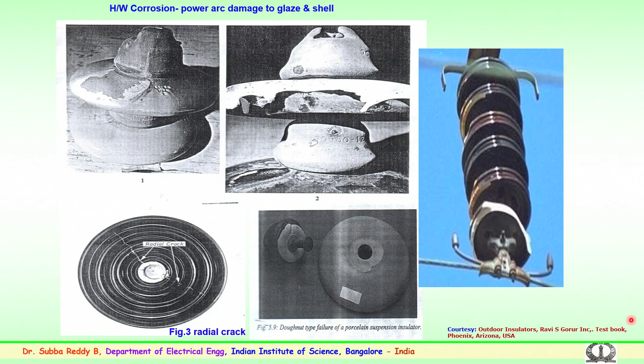This again is a typical example of the lightning phenomenon striking the insulator assembly, where due to the lightning the failure of the insulator assembly has happened. Several of these failure modes have happened due to hardware corrosion. The damage could happen at the pin junction where the Portland cement gives way, or the growth of cement could damage the insulator and help in the puncture of the insulator. So, this has to be clearly taken into consideration before the line is built.